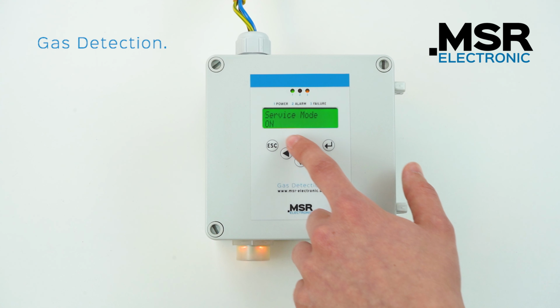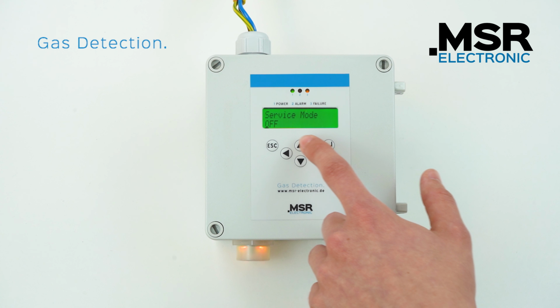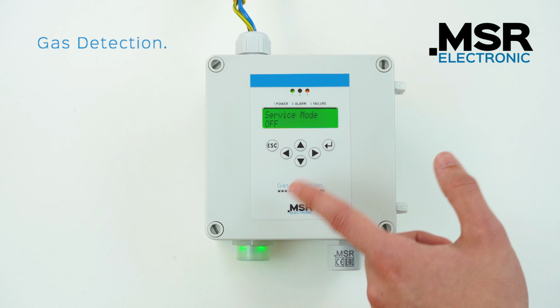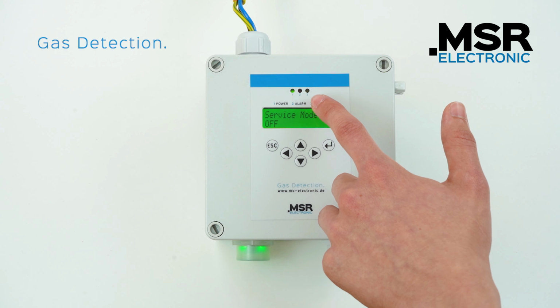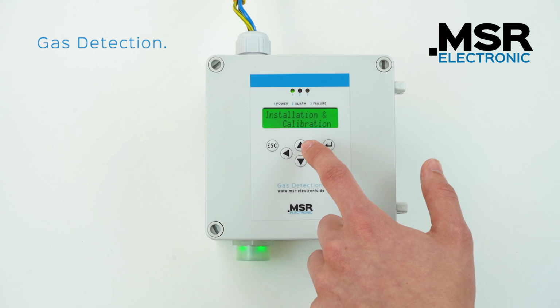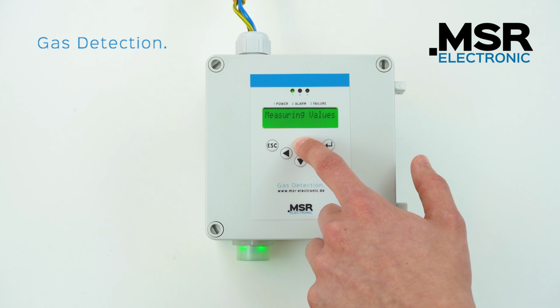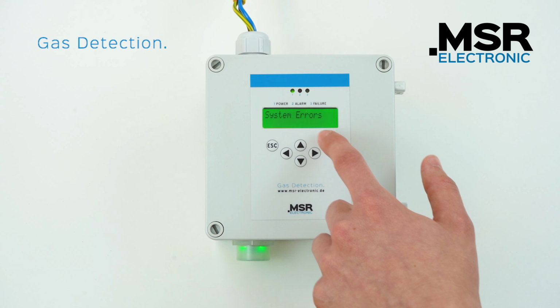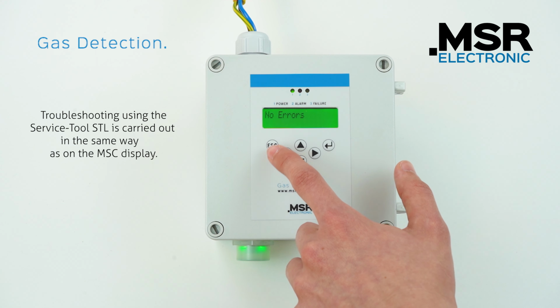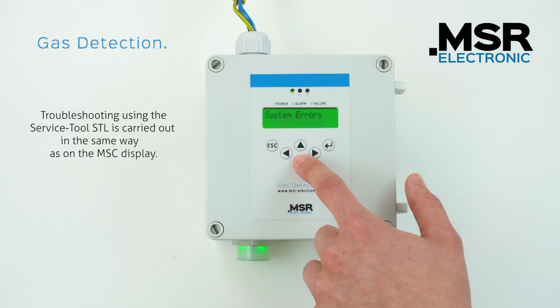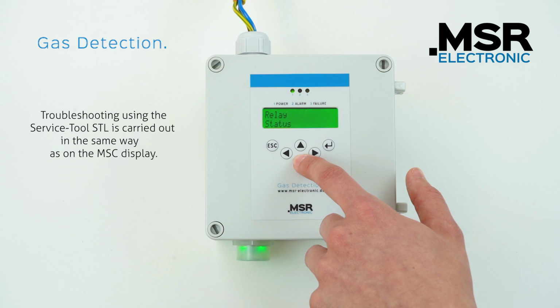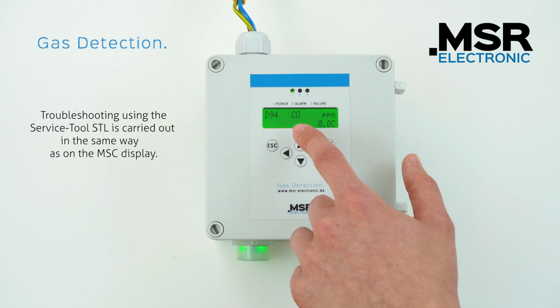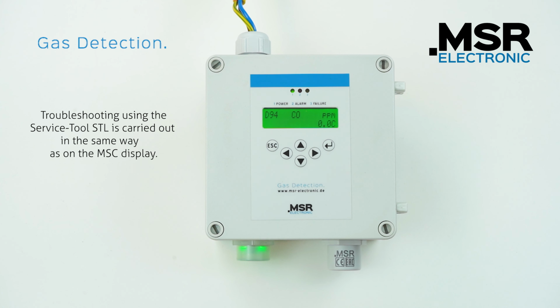Once this has been carried out, you can deactivate the service mode and the yellow LED on the display, or if present on the WAO, goes out and lights up green. The error status now no longer shows any current errors. If you now go to the measured values, the measured value of the sensor is displayed, or if applicable, warm-up time. If this is the case, please wait up to 5 minutes.